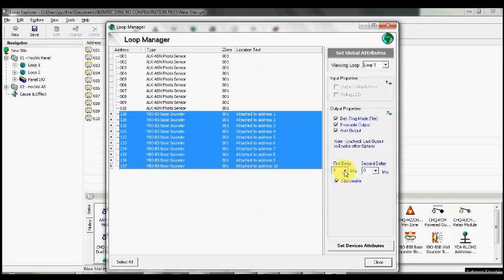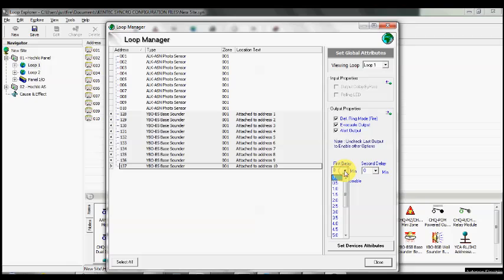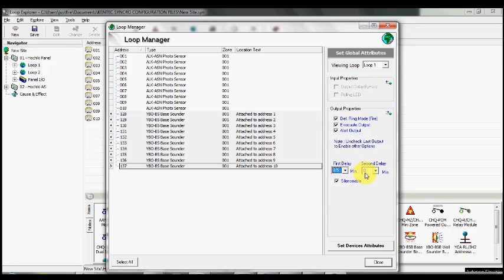We're going to set up the first stage delay. Remember, this is the acknowledgement period, to allow someone to get to the panel to acknowledge it. There'd just be the panel displaying a fire and a local buzzer. Once they push the acknowledgement button, then we go to the investigation delay, the second stage delay.